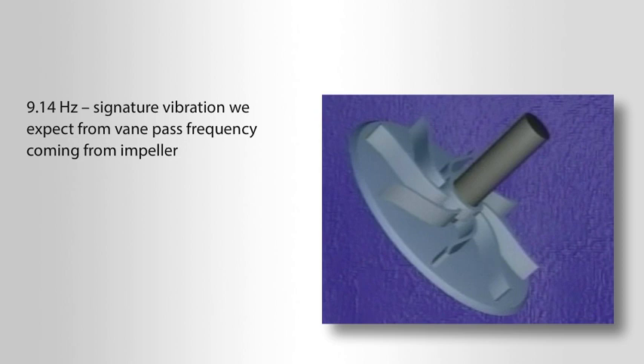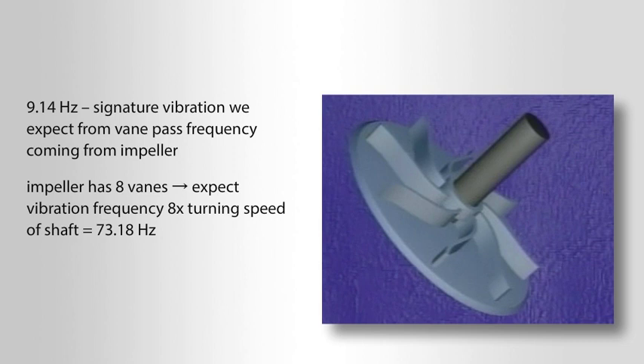The signature vibration we would expect from a pump is a vane pass frequency coming from the impeller. Since this impeller has eight vanes, we would expect a vibration frequency at eight times the turning speed of the shaft, which equals 73.18 Hz.